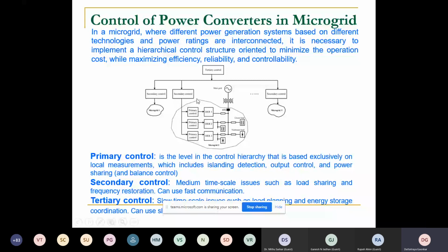In the primary control, you try to adjust the active and reactive power, voltage and frequency. In secondary control, you adjust more finely, and tertiary again finer. If you talk about the time scale, primary control is the fastest, secondary is second, and tertiary is the slowest. That is how the timing response of the control takes place.